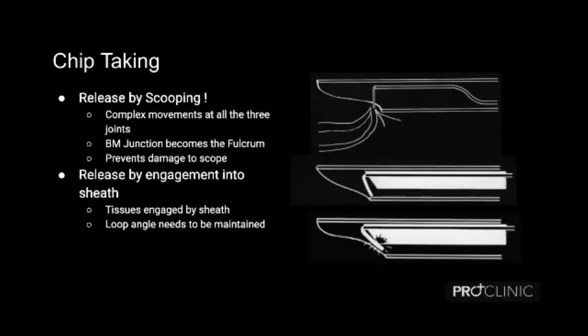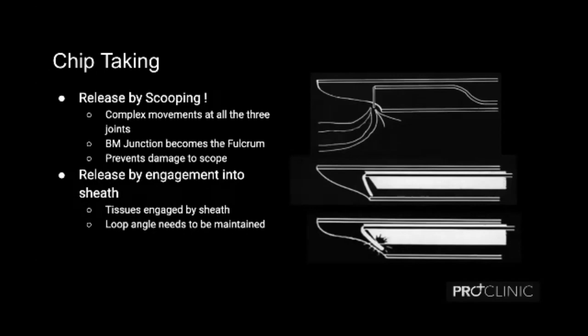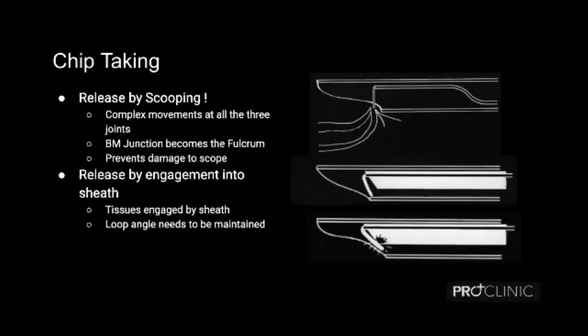There are two ways to take the chip: one is the scooping movement, where before the loop goes inside the sheath we have already completely cut the chip; the other is by engagement into the sheath, where we do not elevate the scope but exploit the mechanics of the instrument itself — when the loop goes inside the sheath it automatically cuts the chip by approximation. Scooping is a better way because it avoids any injury to the cystoscope, and I would want residents to try and use this method for chip taking.